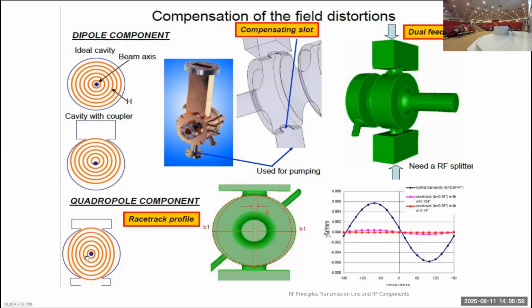But again, you can see instead of circular field lines of magnetic field, these lines are almost elliptical. To cater to these elliptical lines, instead of a circular cavity, we have a slightly elliptic cavity.